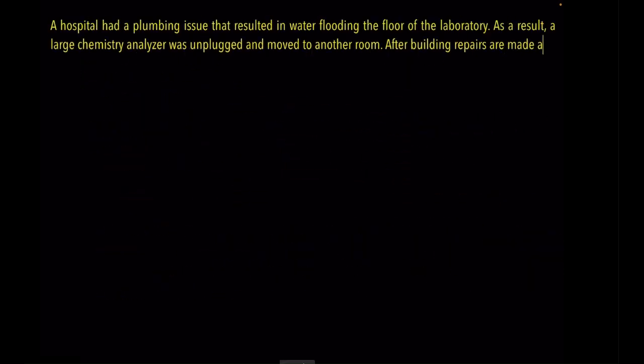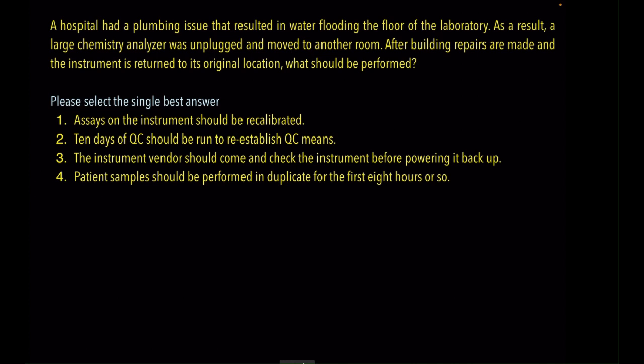A hospital had a plumbing issue that resulted in water flooding the floor of the laboratory. As a result, a large chemistry analyzer was unplugged and moved to another room. After building repairs are made and the instrument is returned to its original location, what should be performed? Please select the single best answer.